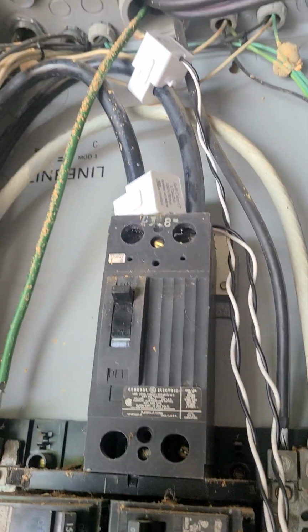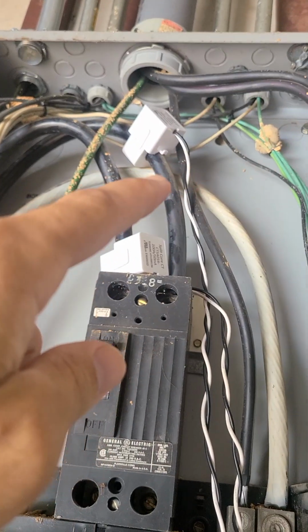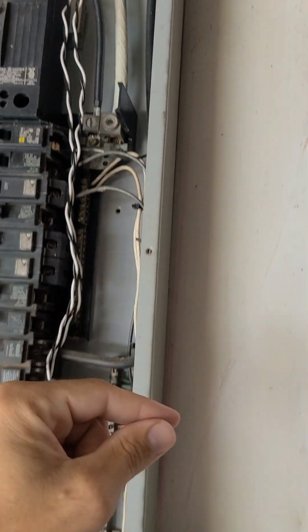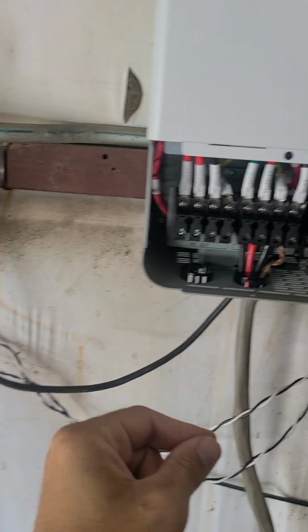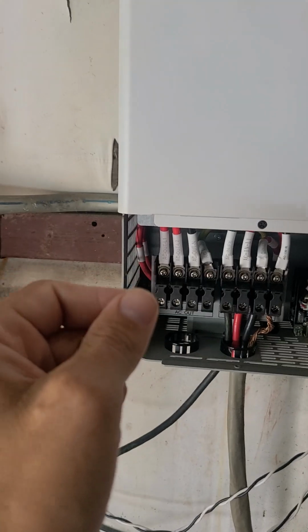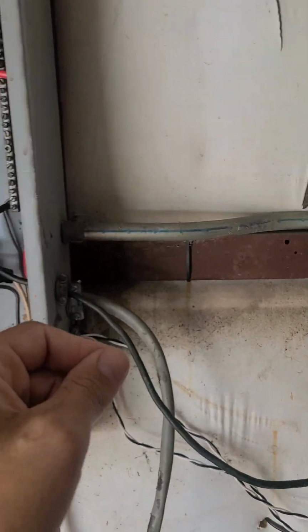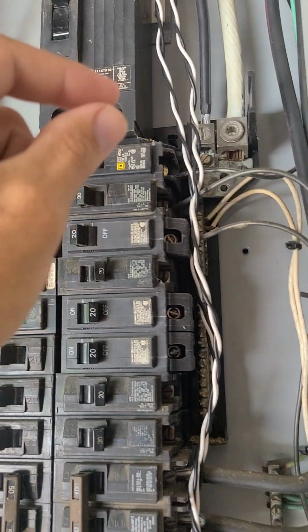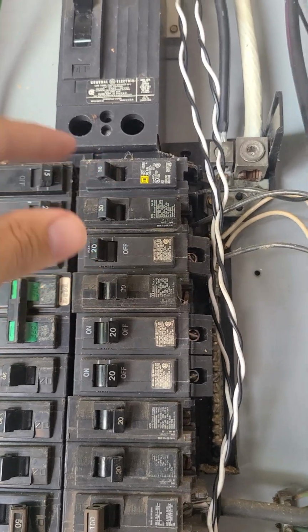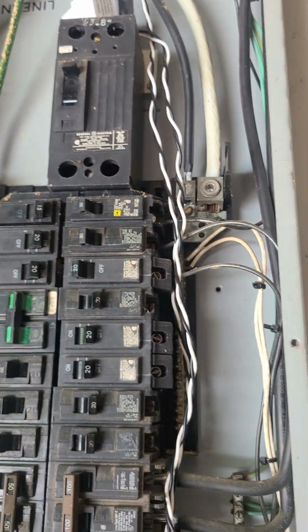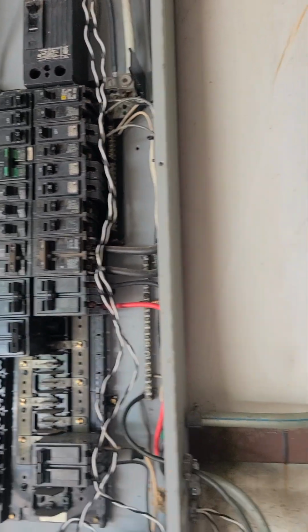This wiring is temporary. I'm eventually going to hook up insulating splice connectors here over to a secondary 60 amp main breaker, and that will run with conduit to the input here, and then our output will run with conduit into here to an interlocked 50 amp right here, so that we'll be an off-grid setup with pass-through.